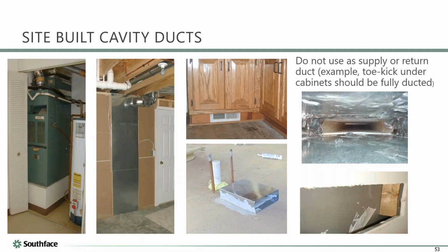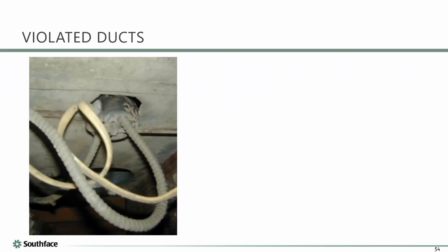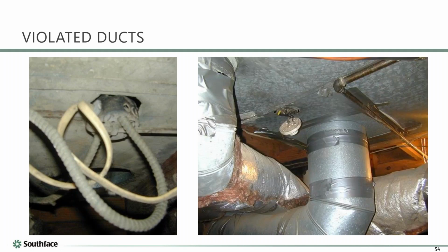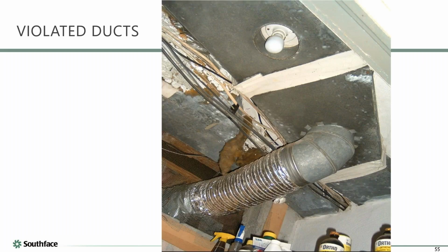And here are some pictures of where, again, we don't want to use building cavities as a duct, like a toe kick, a wall cavity, or a shelf being used as a return duct. Just stay away from that. Bad things happen with those. Who would ever put a light fixture in the middle of a duct? I can't imagine that, and yet I have pictures of it. That's the problem with using floor framing as a duct: somebody else feels like they've got to bust a hole in it. That's not a good thing. And by the way, that is not a legal sealant we're looking at, the gray cloth tubing.